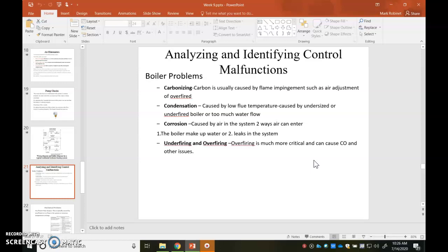Another thing that happens in the boiler is what's called underfiring or overfiring. Overfiring is much more critical and could cause CO and other issues. Underfiring will get you that condensation situation. So a boiler, you want to make sure that it's fired within about 10% of its full input. So if it's 100,000 BTU, you want to fire it between 90 and 100,000 BTU. You do not want to fire it at 110 or 105 or 102. Always underfire a boiler, right?